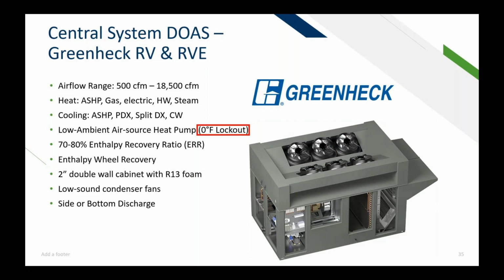So we're kind of shifting gears a little bit, kind of along the lines. This unit right here wouldn't necessarily be compatible with a passive house design. It could be, depending on the enthalpy recovery ratio and sensible effectiveness you get. In a lot of cases, we can get over 75% SRE. So don't rule it out, and let us know if you have that. We could absolutely find you a DOAS no matter what that would work with your system. Just keep that in mind.